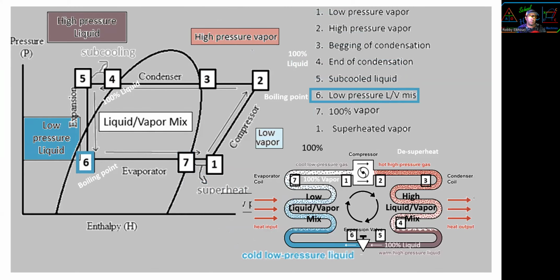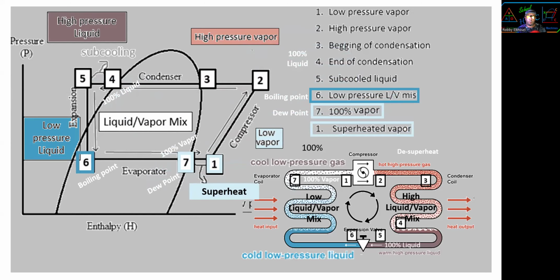Then, I skipped too much. Number 7, 100% vapor, right? That should be the dew point. Yep, dew point. Number 1, superheated vapor. Why? Because between number 7 and number 1, we have a temperature increase. That's your superheated vapor. That's your superheat, 8 to 12. Now the compressor, between 1 and 2, high pressure vapor.